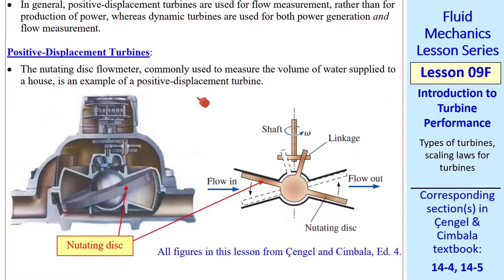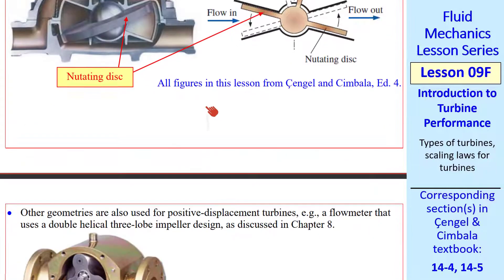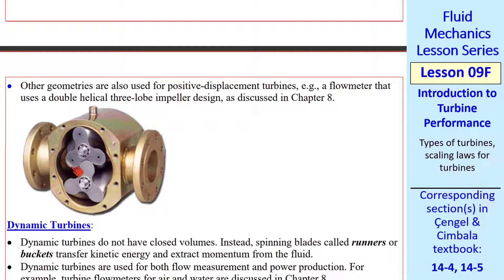Let's talk about positive displacement turbines first. This is a nutating disc flow meter that many of you may have in your house to measure the flow of water. There's a nutating disc that wobbles up and down as it rotates. There's a certain amount of volume that comes into this fixed volume or lobe, and as it wobbles and rotates, it pushes that flow out. Here's a turbine with a double helical, three-lobed impeller. The output shaft is not producing power — it's a flow meter, so the shaft turns a counting device or tachometer.